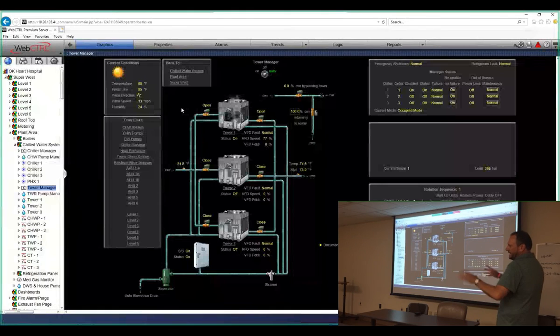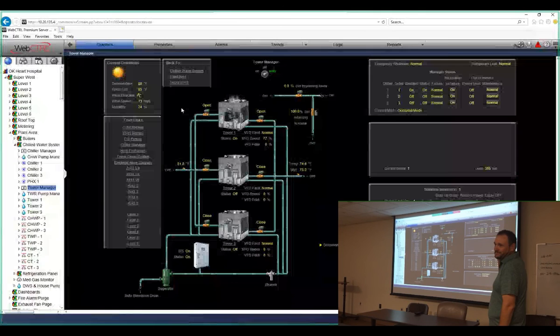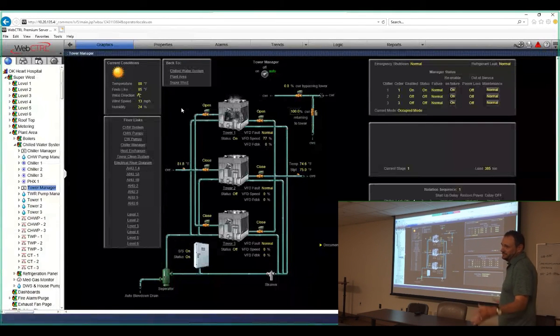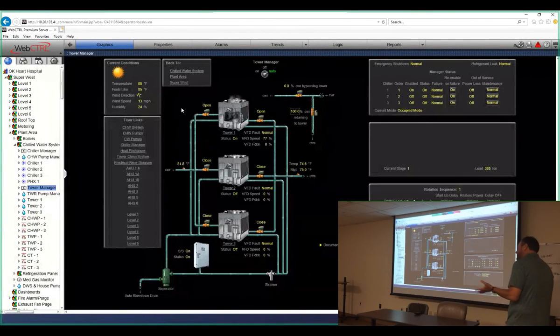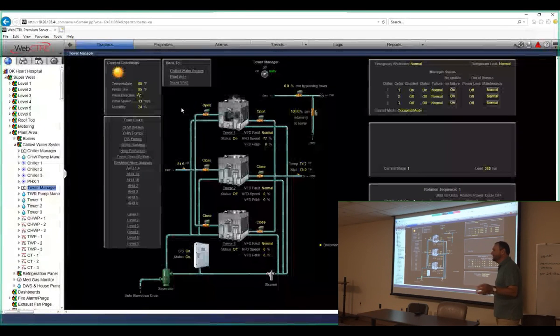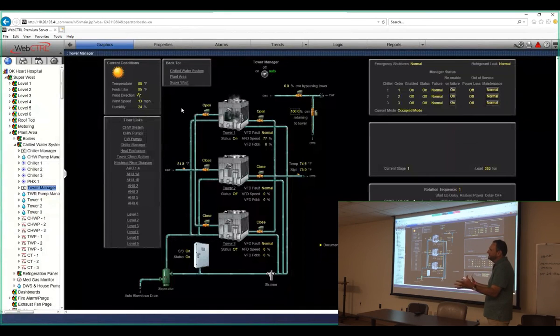Anyway, that's a pretty high level of this kind of stuff. Corey's going to get into the weeds and really talk about the plant stuff next week. But the majority of the time, until winter gets here, you're probably going to see 2 chill water pumps, 1 chiller, 1 condenser water pump, and 1 tower. Until we hit the 90s. When we get into the 90s, we're going to have 2 chillers, 2 condenser water pumps, 2 towers, and still 2 chill water pumps.